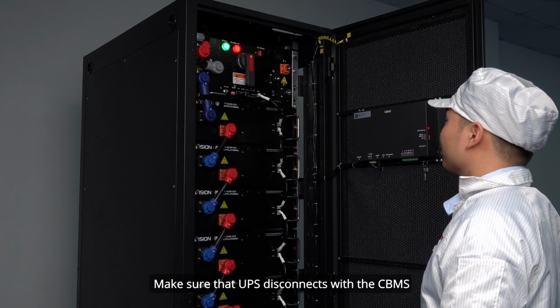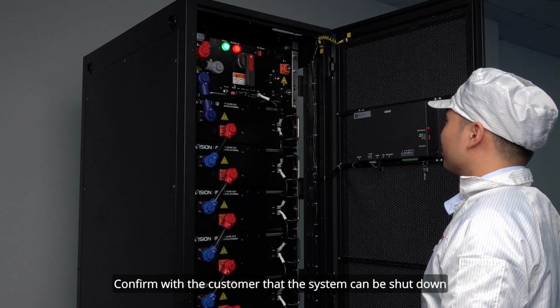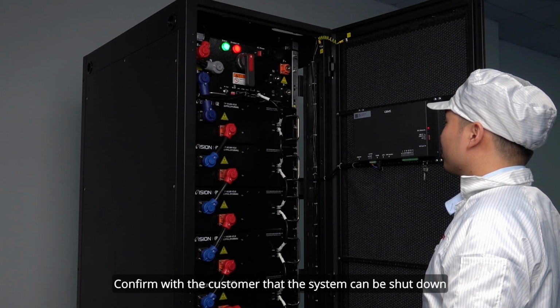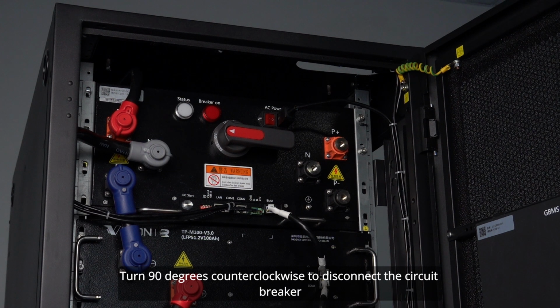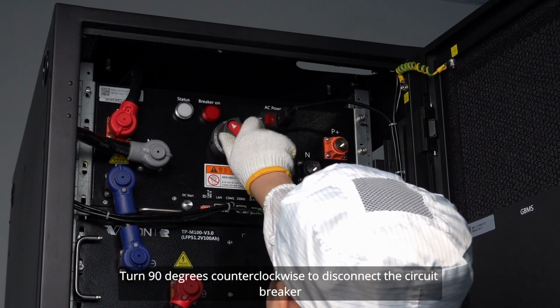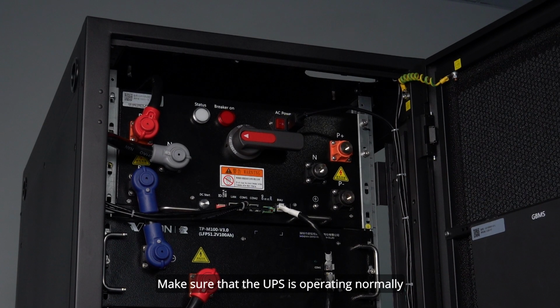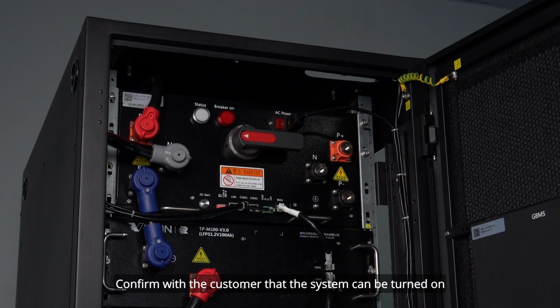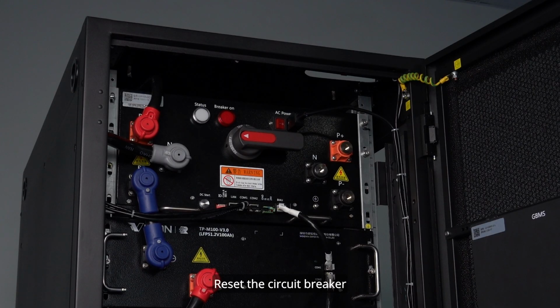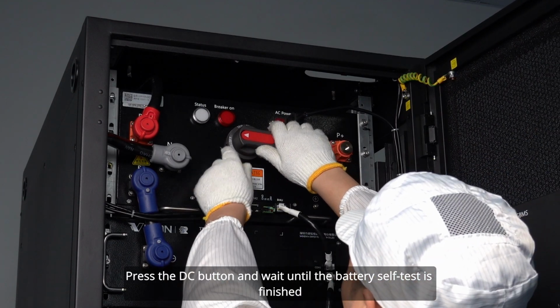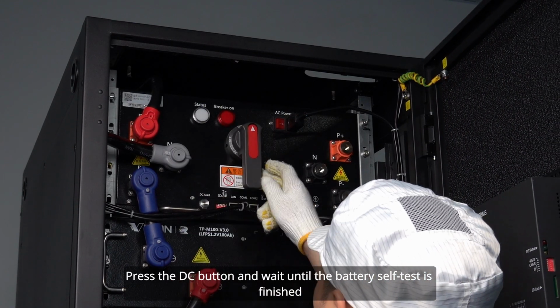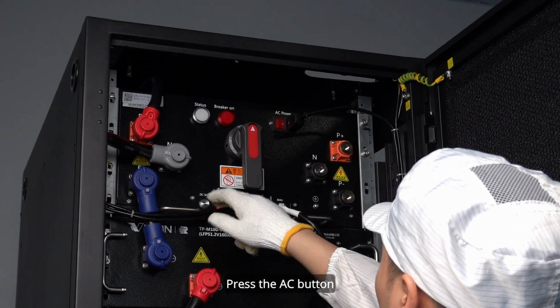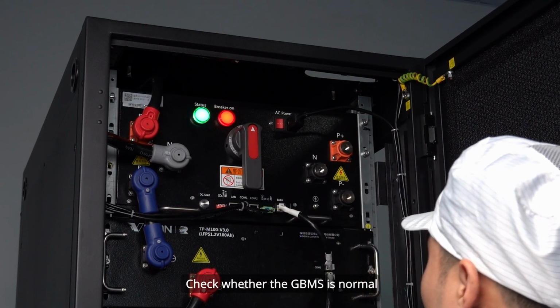Step 4. Discharging. Make sure that UPS disconnects with the CBMS. Confirm with the customer that the system can be shut down. Turn 90 degrees counterclockwise to disconnect the circuit breaker. Step 5. Recharging. Make sure that the UPS is operating normally. Confirm with the customer that the system can be turned on. Reset the circuit breaker. Press the DC button and wait until the battery self-test is finished. Press the AC button. Check whether the GBMS is normal.